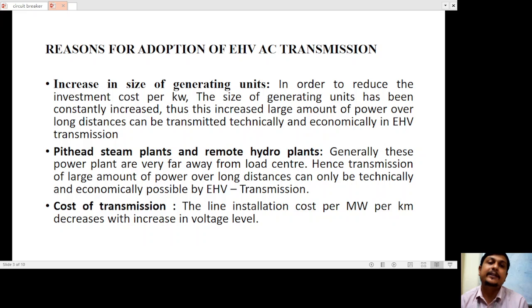Second reason: pithead steam power plants and remote hydro plants are generally located far from the load center. Hence, transmission of large amounts of power over long distances is only feasible with EHV transmission. If you transmit at lower voltage, you may see around 60 to 70% losses, transmitting only 30% of power, and the cost will increase accordingly.